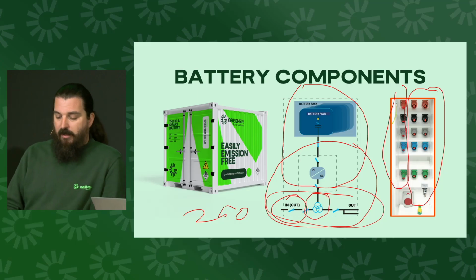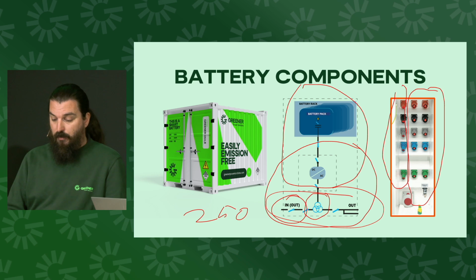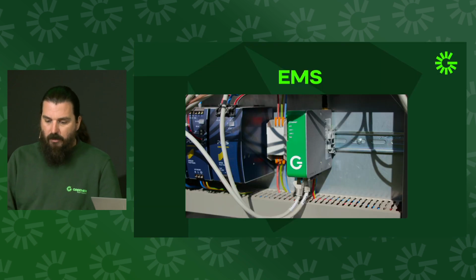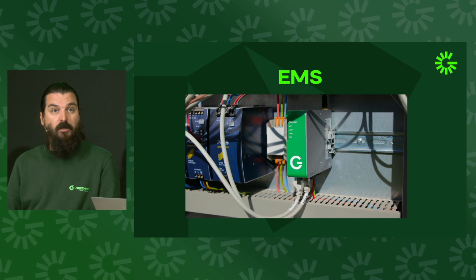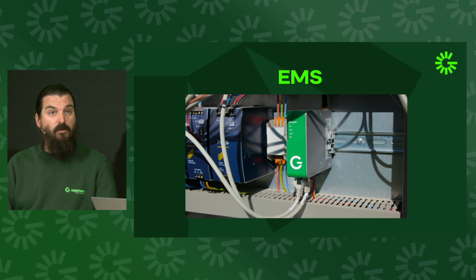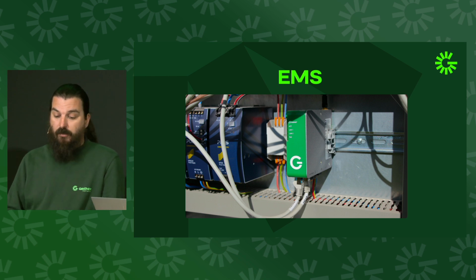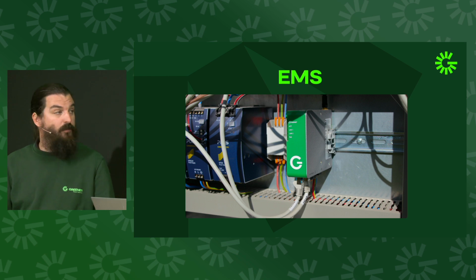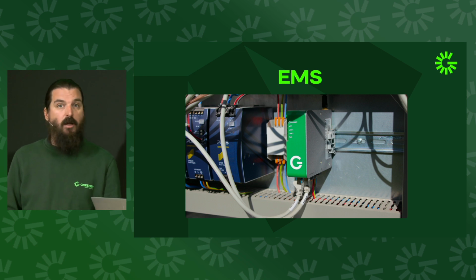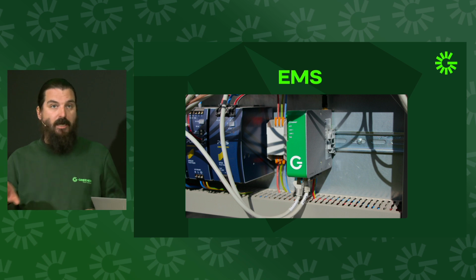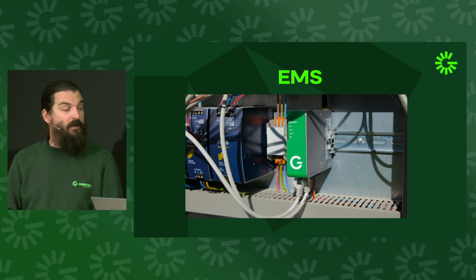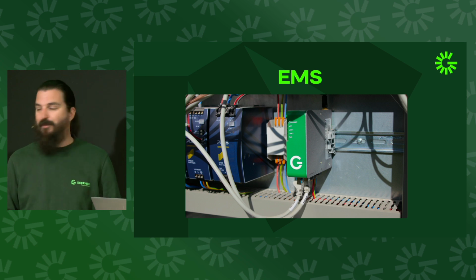And then when you've got all of this very nice OEM hardware, it actually needs to be controlled. So we have a Greener Eye, which holds our EMS system, which is a bit of software that we write ourselves and control ourselves. And then with that, we control all the bits and pieces, read and write all the bits and pieces which are in the battery system. Amongst others, the inputs and the outputs are completely measured out, so we know exactly the amount of power that's flowing over the single phases and over the total, which of course you need in order to do energy balance, to calculate what the inverter needs to do.